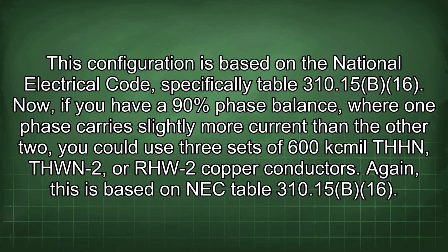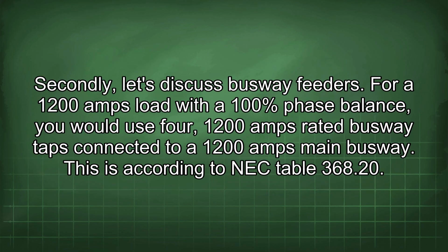Now, if you have a 90% phase balance, where one phase carries slightly more current than the other two, you could use 3 sets of 600 kcmil THHN, THWN-2, or RHW-2 copper conductors. Again, this is based on NEC Table 310.15(B)(16).